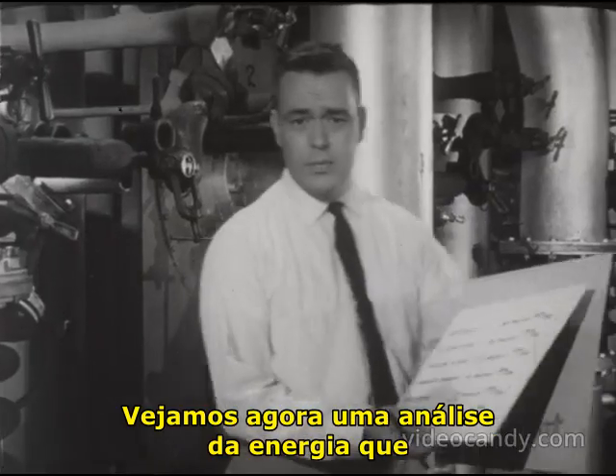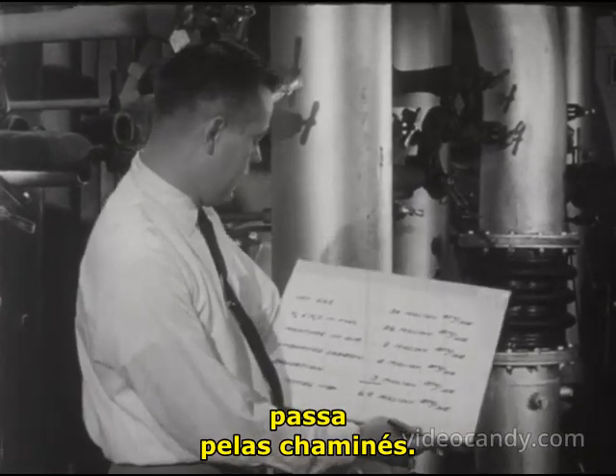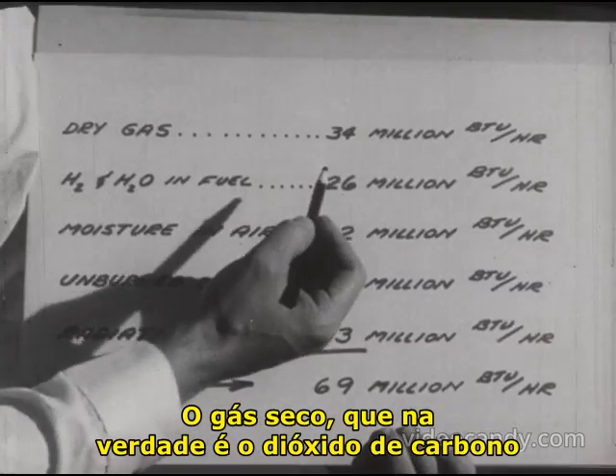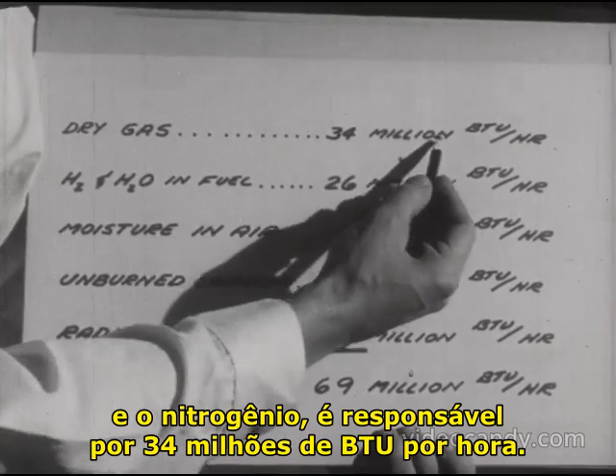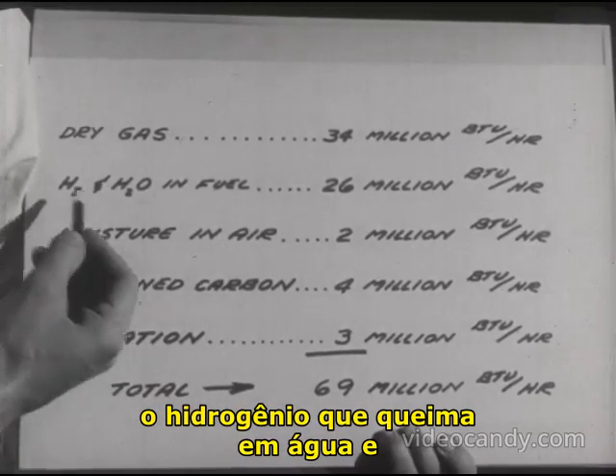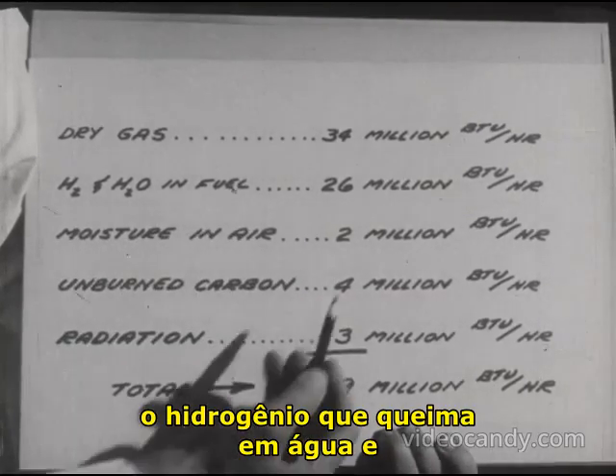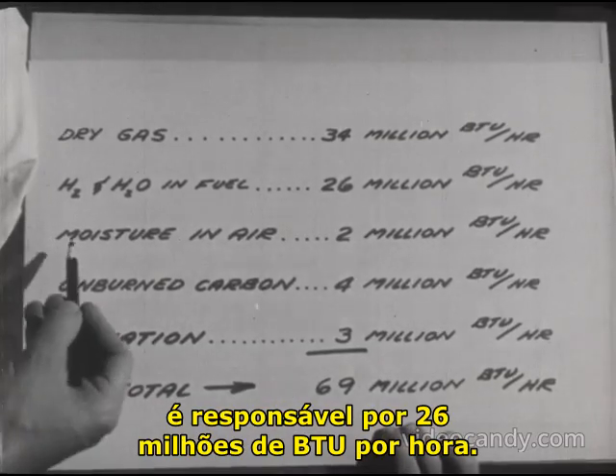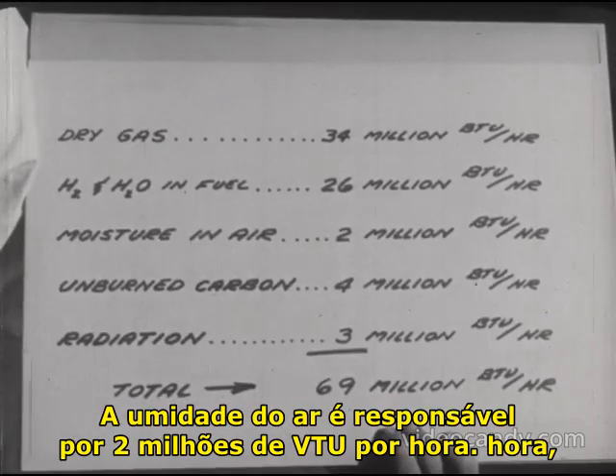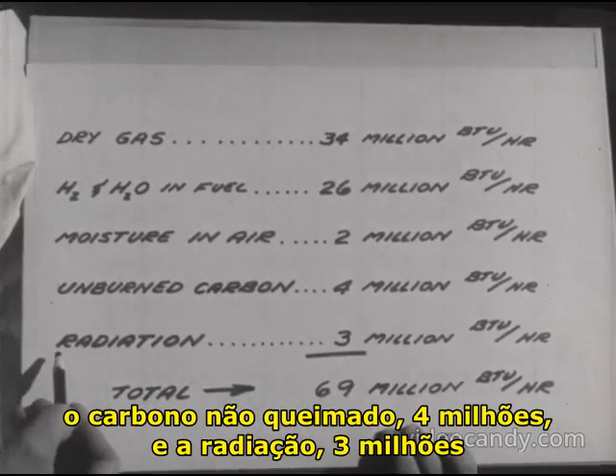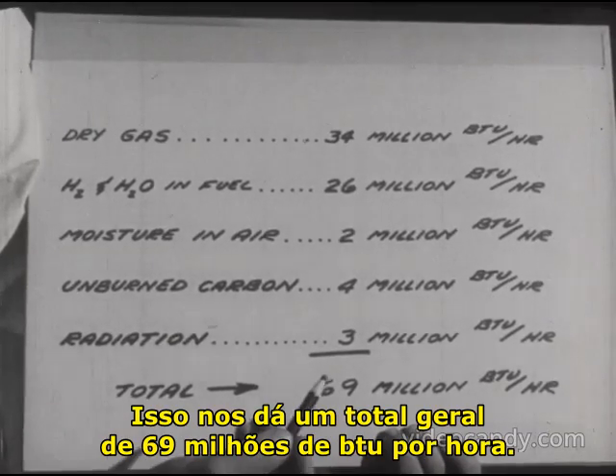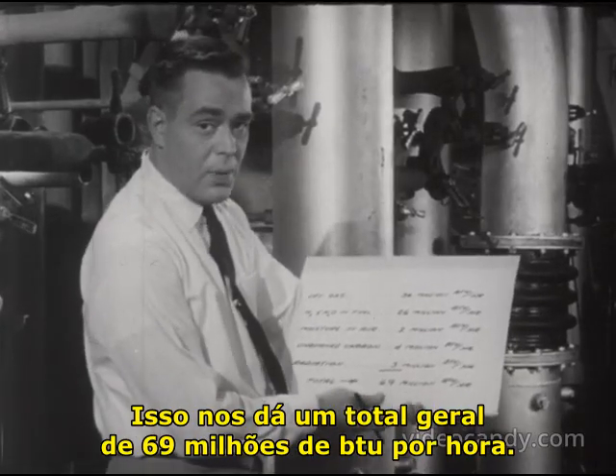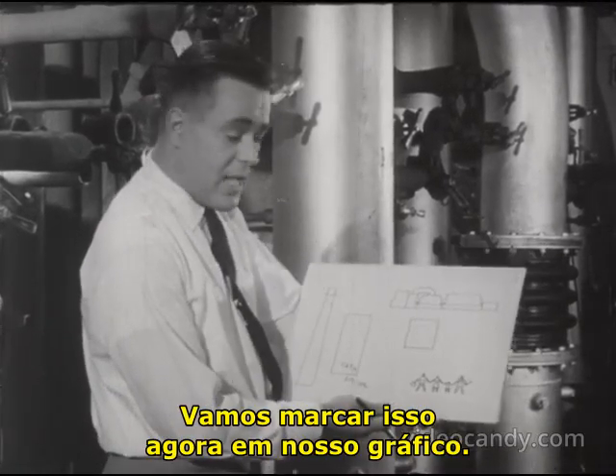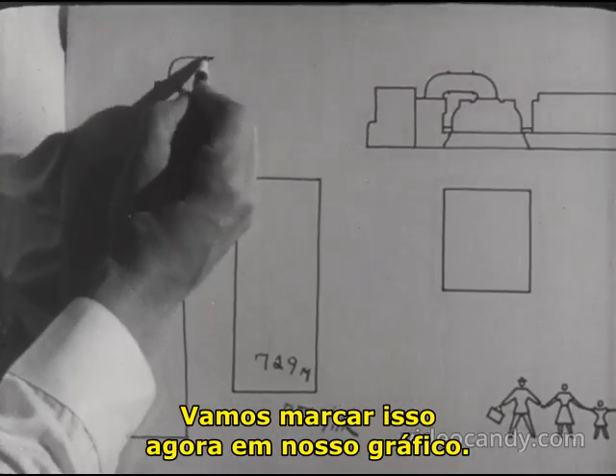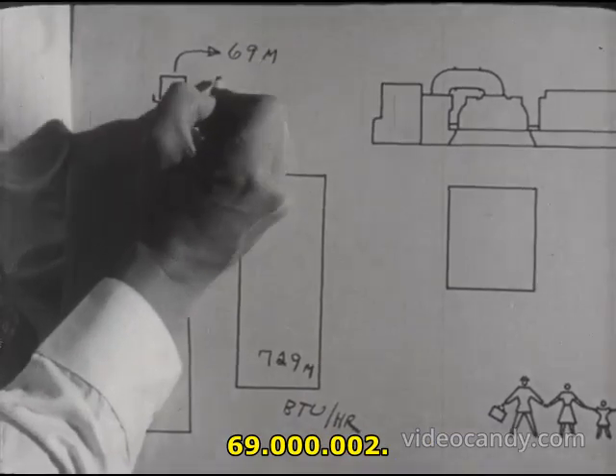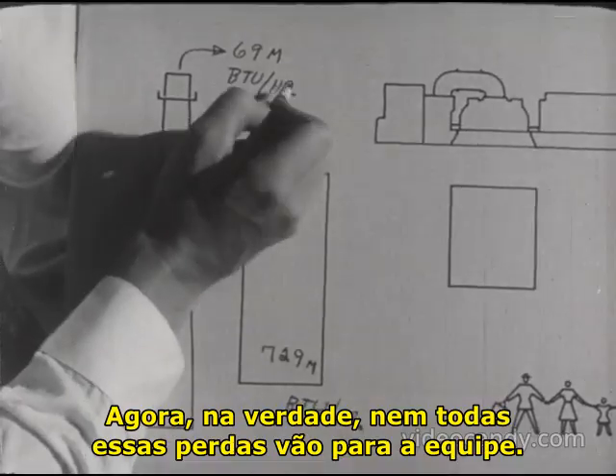Let's look now at a breakdown of the energy that passes out through the stack. The dry gas, which is actually the carbon dioxide and the nitrogen, accounts for 34 million BTU per hour. The hydrogen, which burns to water, and the water in the fuel, accounts for 26 million BTU per hour. The moisture in the air accounts for 2 million BTU per hour. The unburned carbon, 4 million, and the radiation, 3 million BTU per hour. This gives us a grand total of 69 million BTU per hour. Let's mark this down now on our chart and show this passing out of the stack. 69 million BTU per hour.